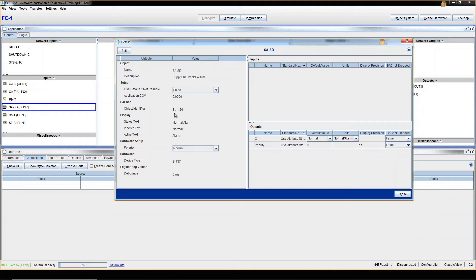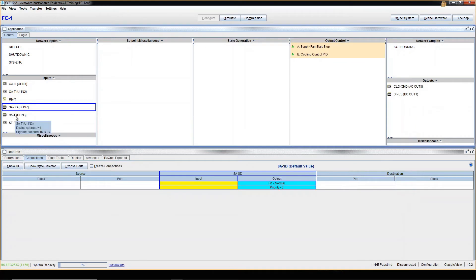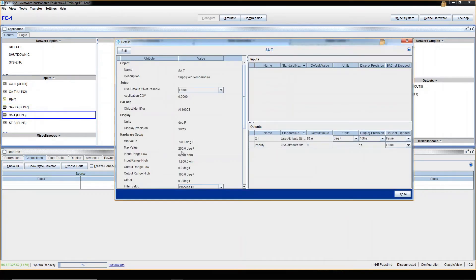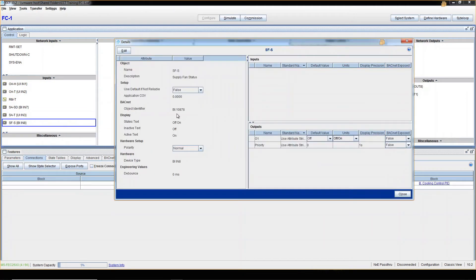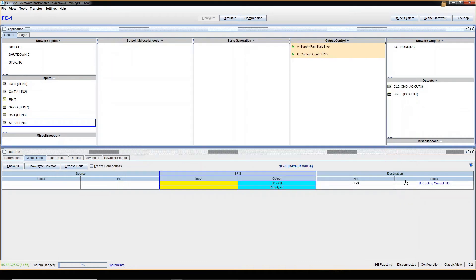These physical temperature inputs are all Analog Inputs (AI). Next, Supply Air Smoke Alarm — this is a Binary Input (BI). Binary means two states, but when talking about physical inputs, they are always going to be Enumerators, not Booleans — typically two-state Enumerators. Supply Fan Status is also a Binary Input, which is also an Enumerator with two states only.